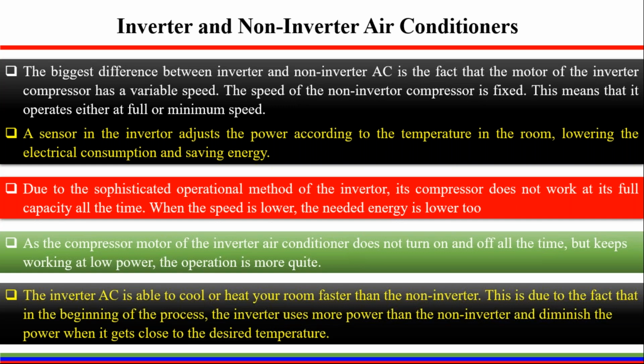There's a sensor in the inverter air conditioner that adjusts the power according to the temperature in the room. In the non-inverter air conditioners, when the compressor reaches its design temperature, it shuts down, and when the temperature rises above the design temperature, the compressor starts. But in the inverter air conditioner, the compressor never stops. It has variable speeds. When it reaches the design temperature, its speed slows down. And when the temperature of the room rises up, the speed of the compressor motor increases step by step. That's why it does not go at the highest speed or the lowest speed.